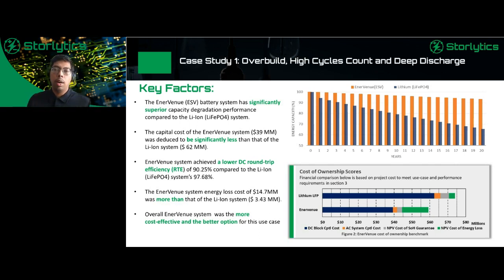So another aspect is to quantify this impact or difference in round trip efficiency, which is captured in the energy loss. As we know, battery systems don't generate their own energy. They store energy, and in the process there are some losses. So that loss needs to be accounted for in the overall cost of the project.